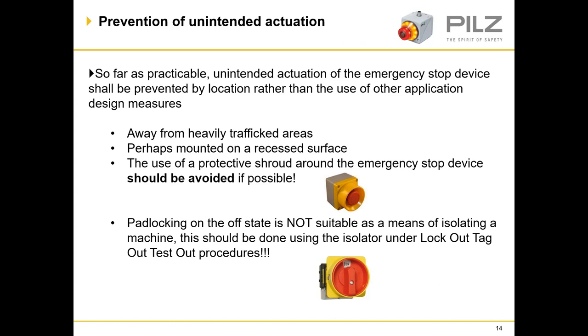Prevention of unintended actuation: so far as practicable, unintended actuation of the emergency stop device shall be prevented by location rather than other application design measures. Emergency stops should be positioned away from heavily trafficked areas, mounted perhaps on a recessed surface within the machine, but the recess should be big enough for a full hand to actuate the e-stop. The use of a protective shroud around e-stops should be avoided, as mentioned in standard 13850. Before shrouding an e-stop, you should consider the position and relocate it away from heavily trafficked areas where it could be triggered by accident.